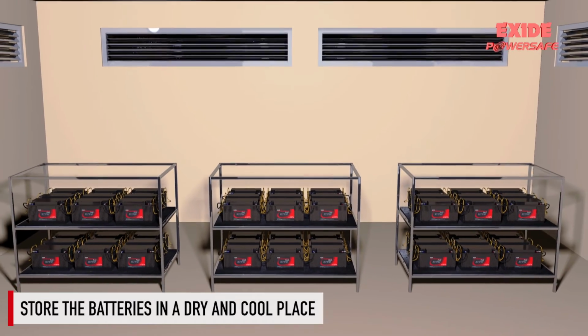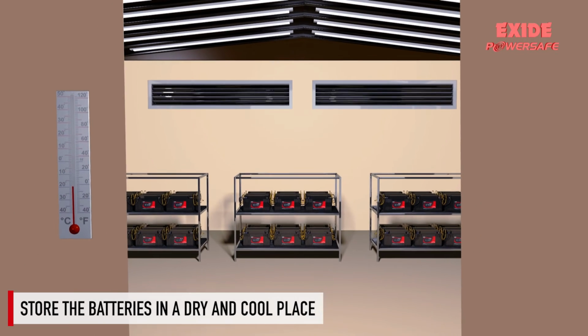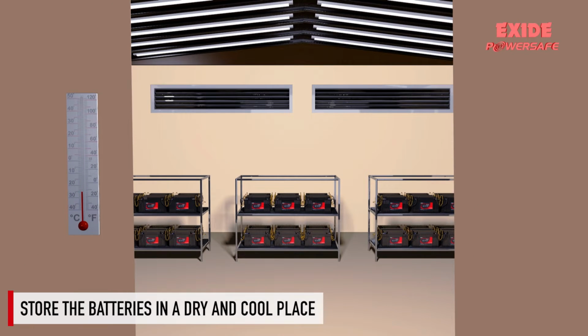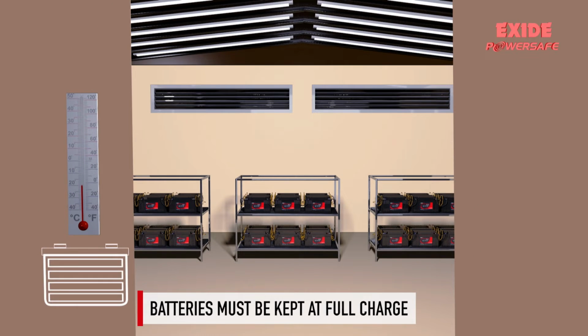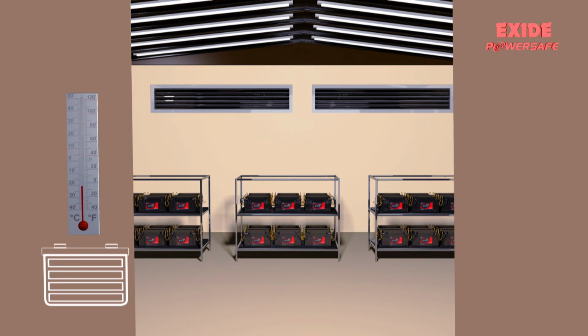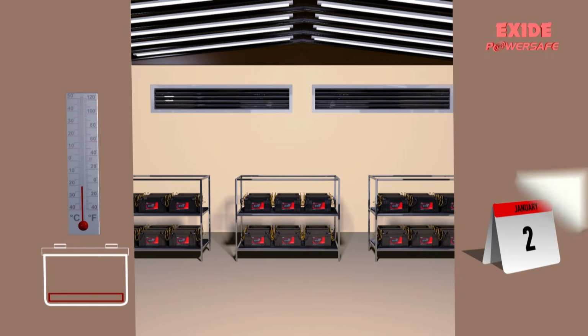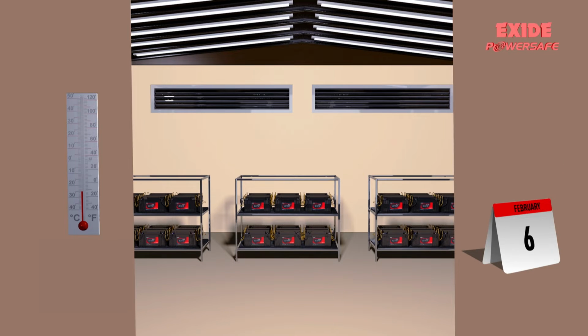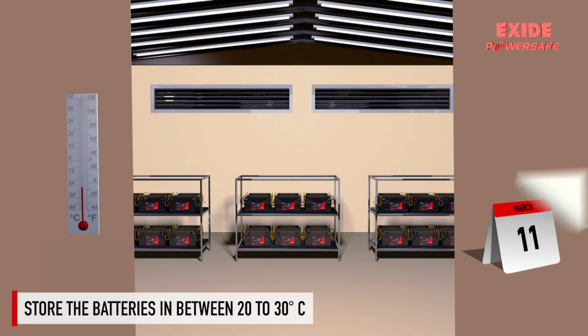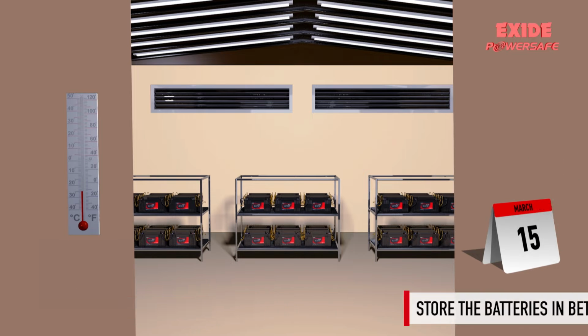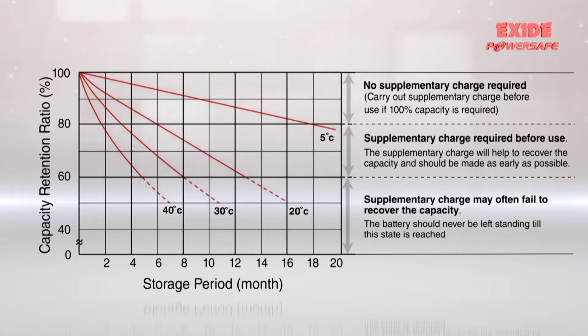Store the batteries indoor in a dry and preferably cool location away from any source of heat or fire. Lead-acid batteries must always be kept at full charge during storage. Storage will cause batteries to self-discharge. The rate of self-discharge increases with temperature. In order to achieve 3 to 6 months of shelf life, the batteries should be stored between 20 to 30 degrees Celsius. Based on the storage temperature and duration, supplementary charging intervals should be decided as shown in the graph to avoid permanent capacity loss.